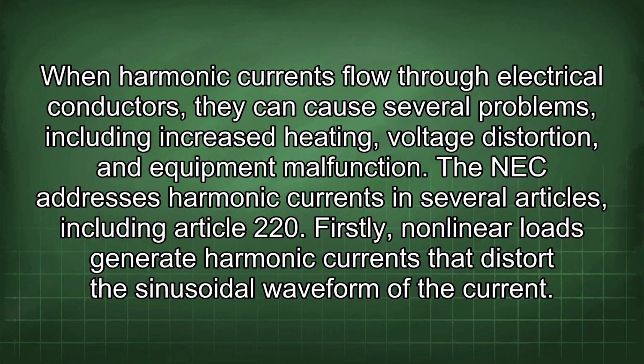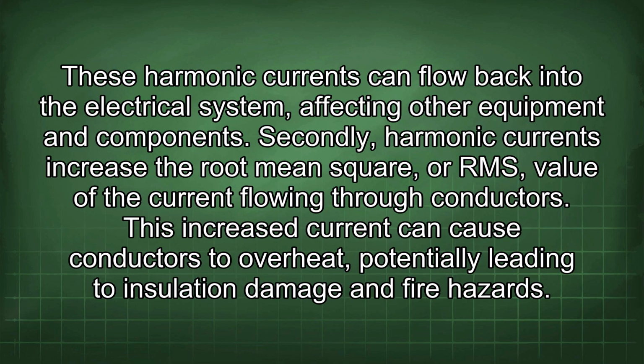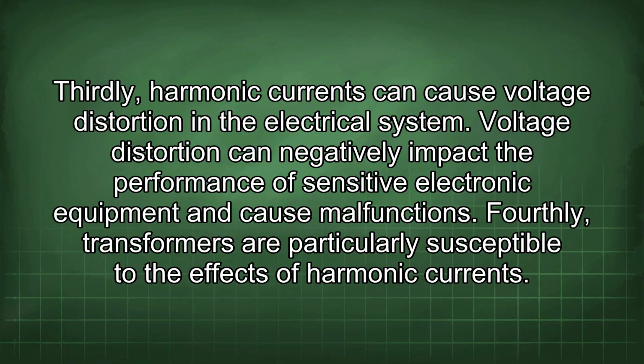Firstly, nonlinear loads generate harmonic currents that distort the sinusoidal waveform of the current. These harmonic currents can flow back into the electrical system, affecting other equipment and components. Secondly, harmonic currents increase the root mean square, or RMS, value of the current flowing through conductors. This increased current can cause conductors to overheat, potentially leading to insulation damage and fire hazards. Thirdly, harmonic currents can cause voltage distortion in the electrical system. Voltage distortion can negatively impact the performance of sensitive electronic equipment and cause malfunctions.